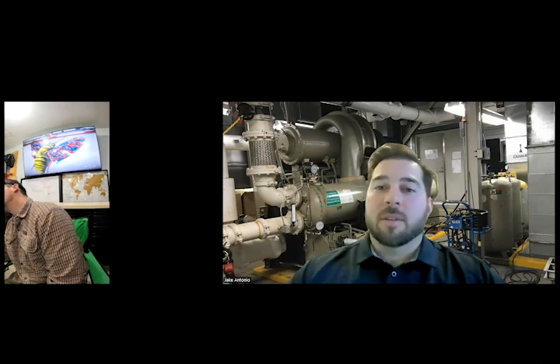Behind me on my screen here is one of the job sites I worked at, and I was taking the refrigerant out of the system. This is a Trane chiller, and I was taking out the refrigerant R123. There's some of the equipment behind me there - the low pressure recovery machine, which is just a big vacuum pump essentially with a few other components. Then there's a couple of tanks back there - we got two 550-pound cylinders, and a 1,000-pound cylinder over there. So I was taking the refrigerant out of this chiller using the push pull method.